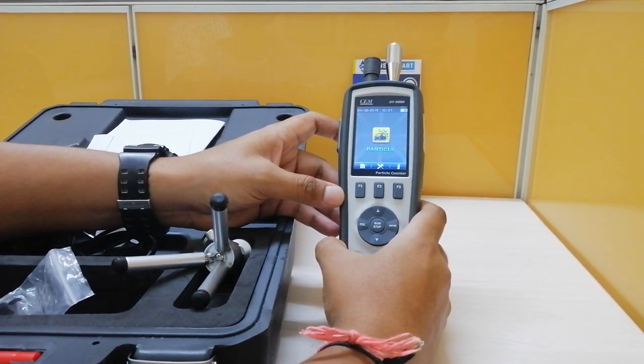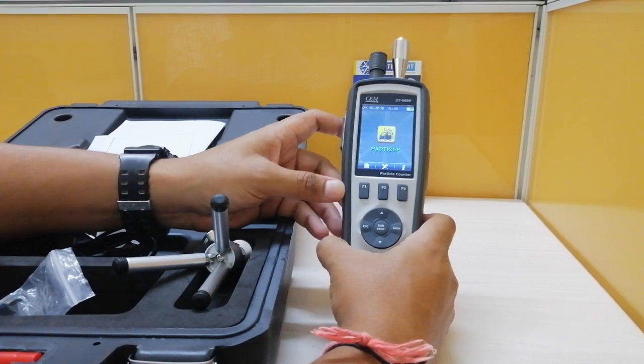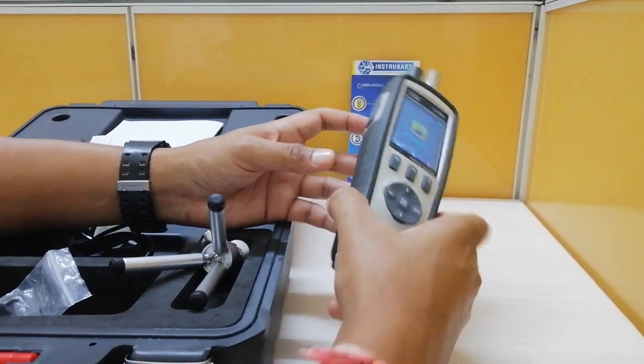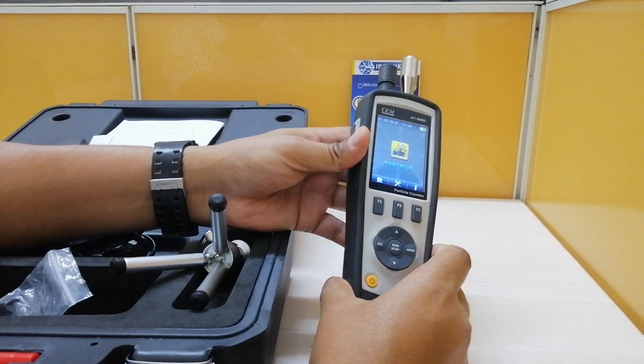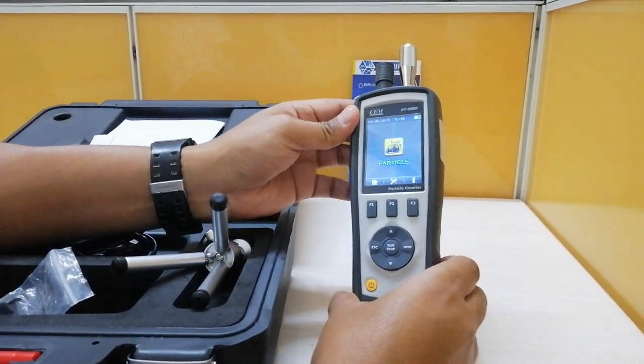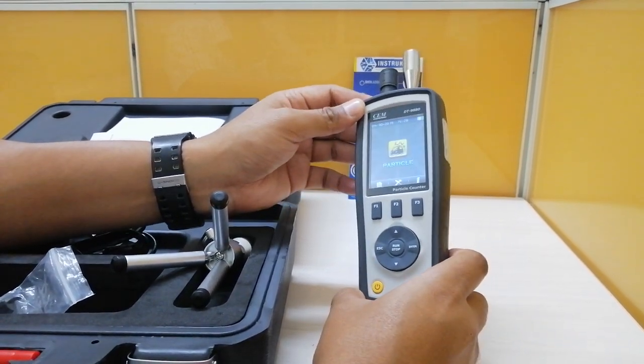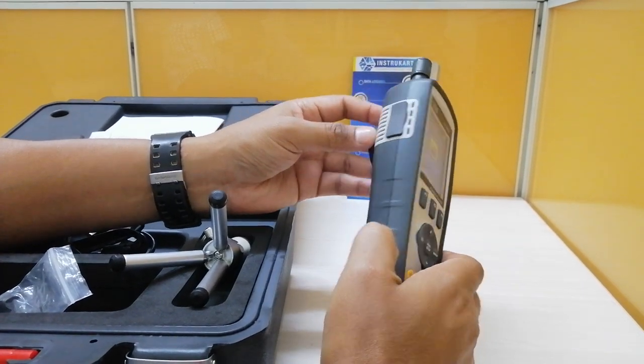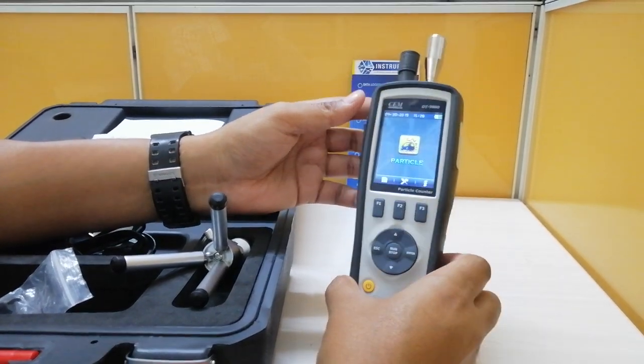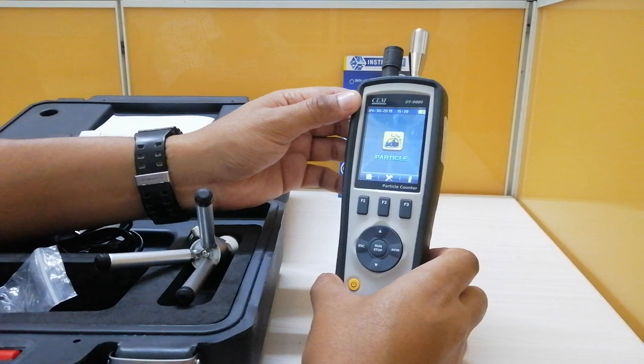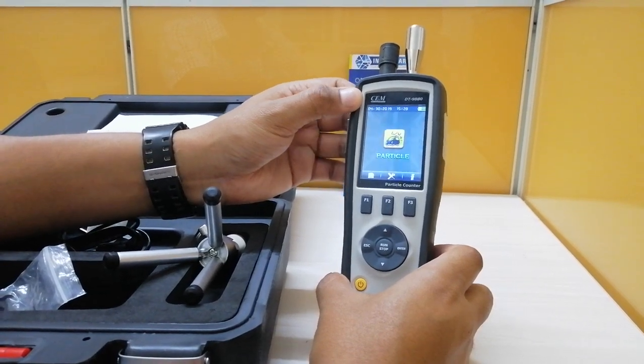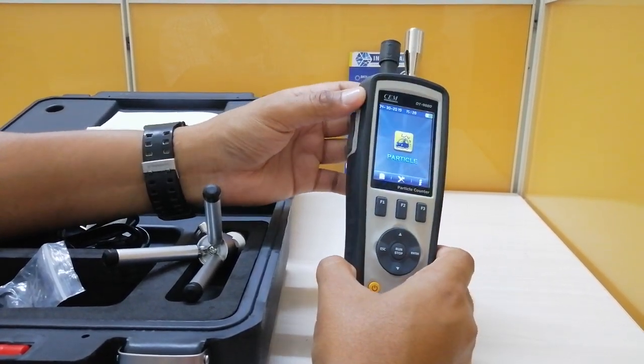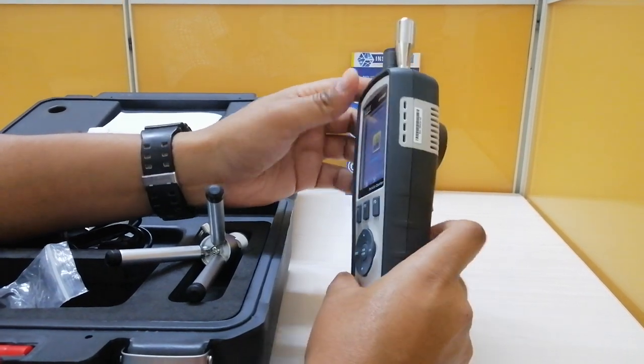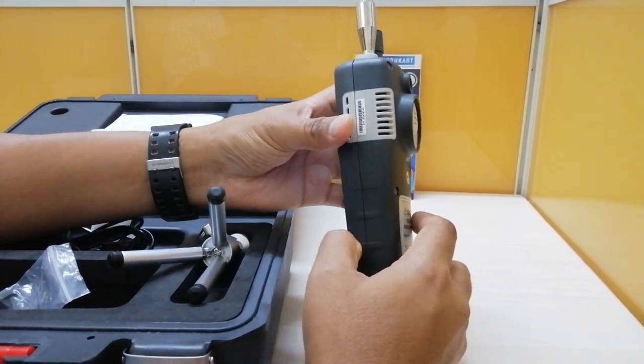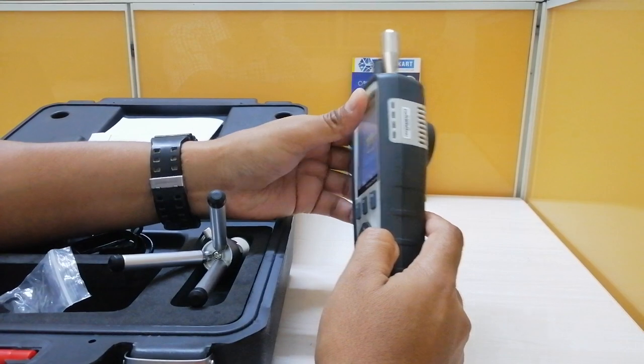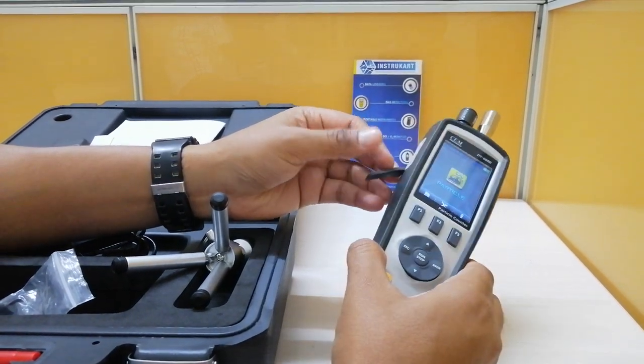For the temperature and humidity measurement, it has a temperature range of 0 to 50 degrees Celsius, which is 32 to 122 degrees Fahrenheit, with an accuracy of plus or minus 0.5 degrees Celsius. The humidity range is 0 to 100 with a basic accuracy of plus or minus 2.5%. The dew point temperature is minus 30 to 100 degrees Celsius, and the wet bulb temperature range is 0 to 80 degrees Celsius.